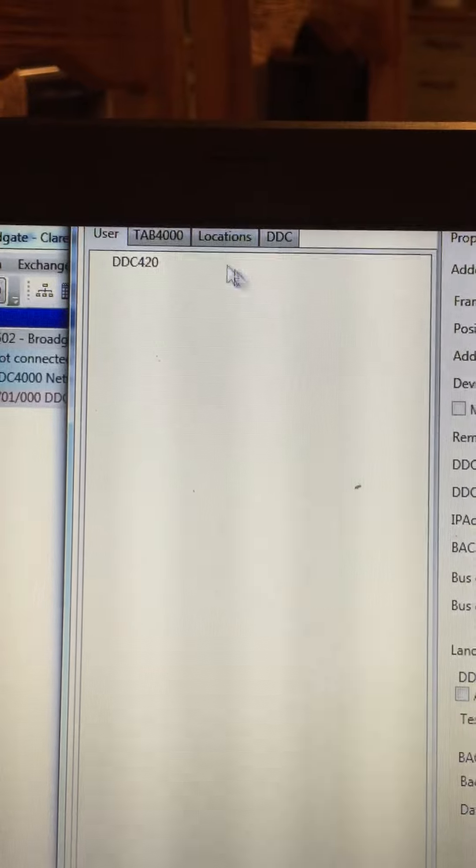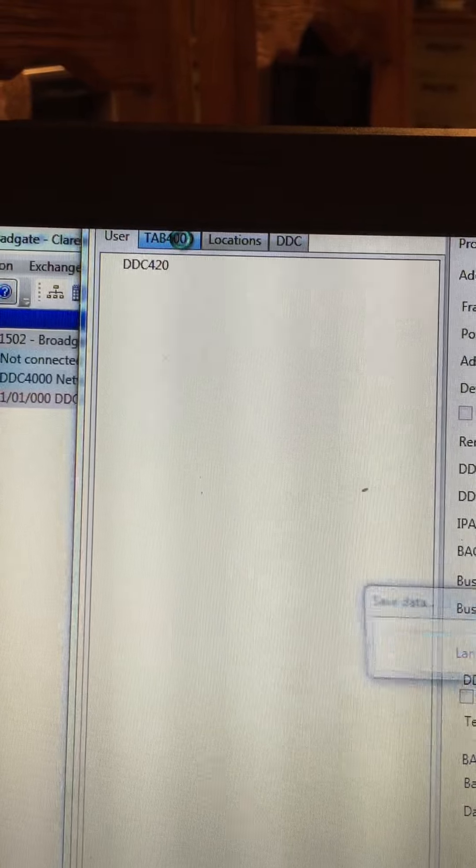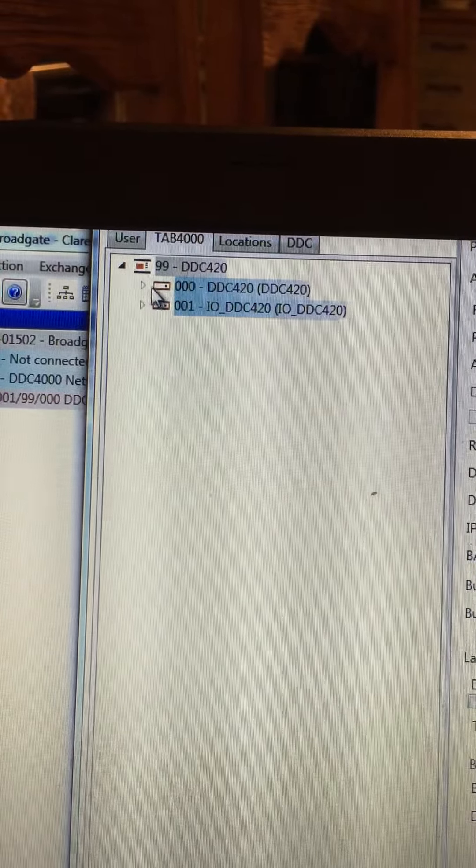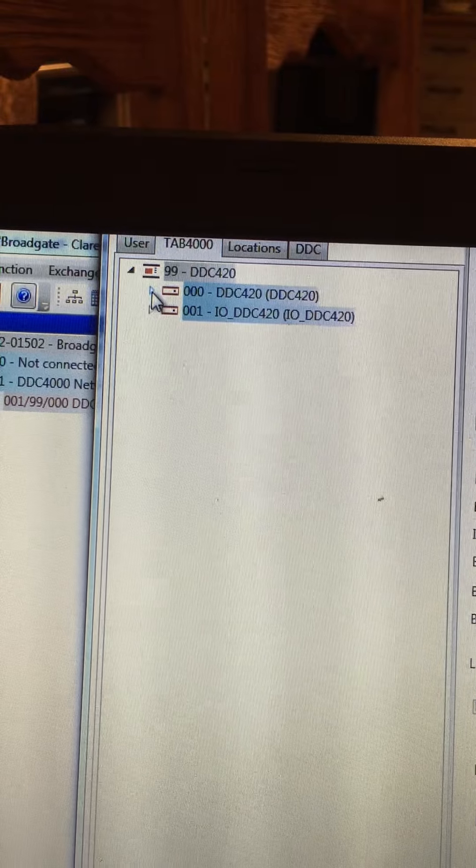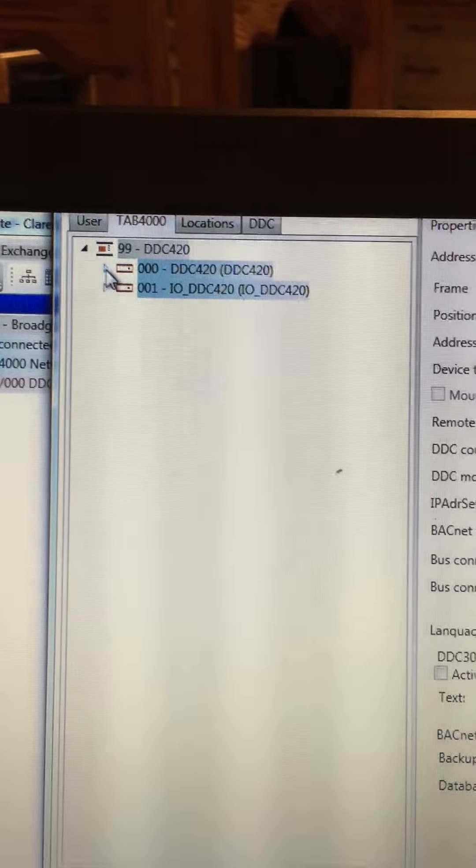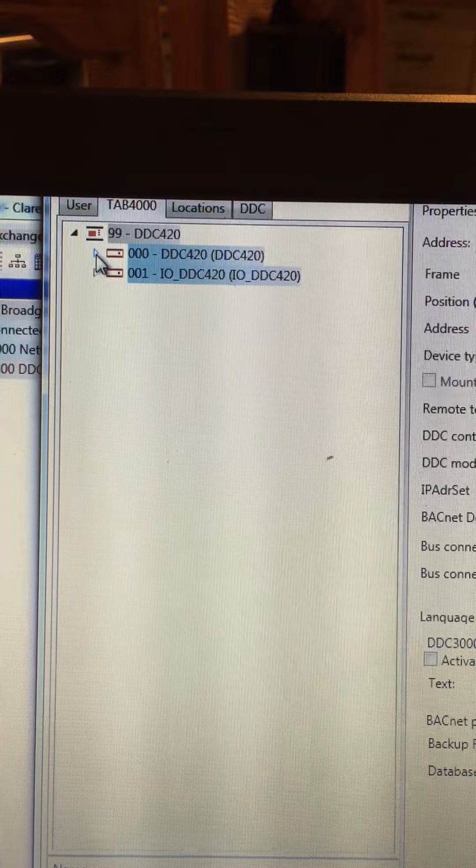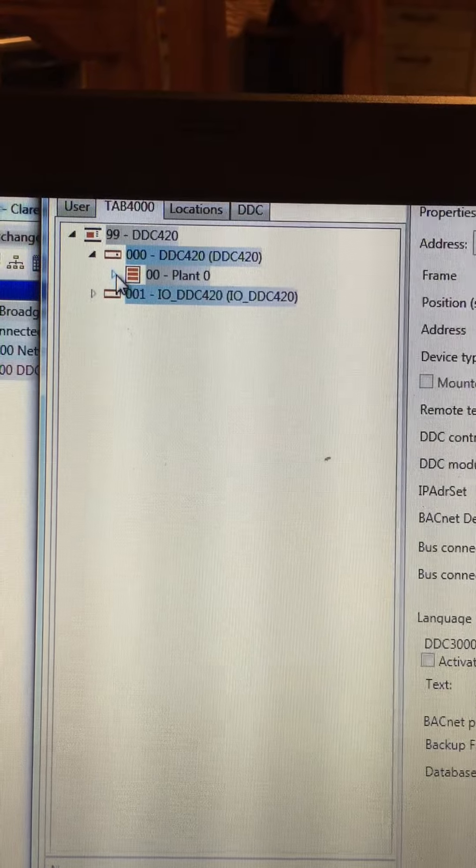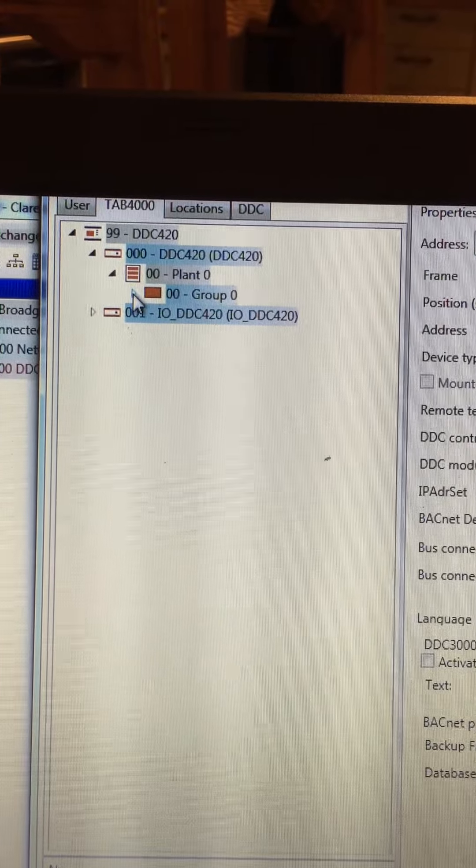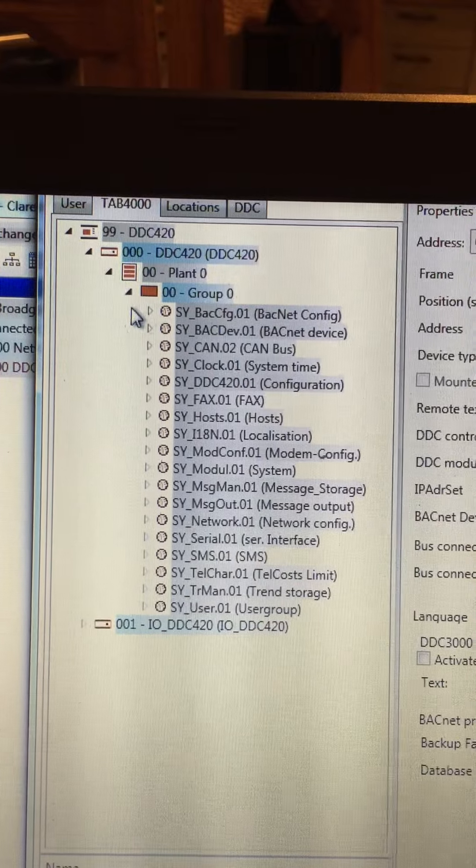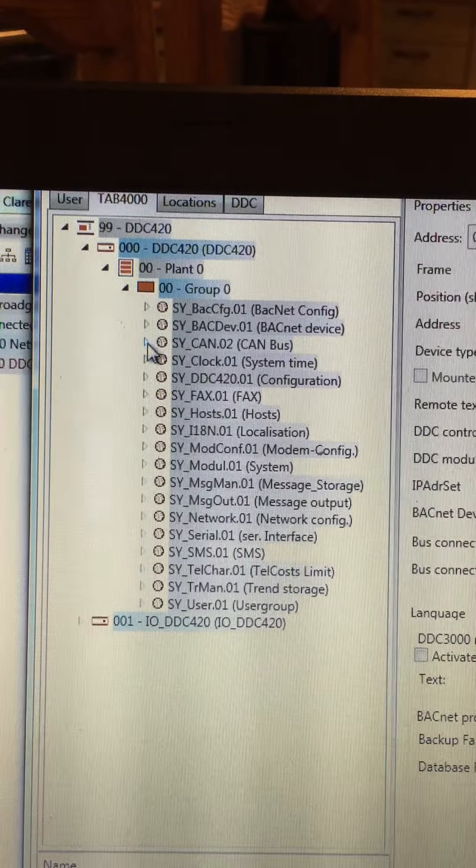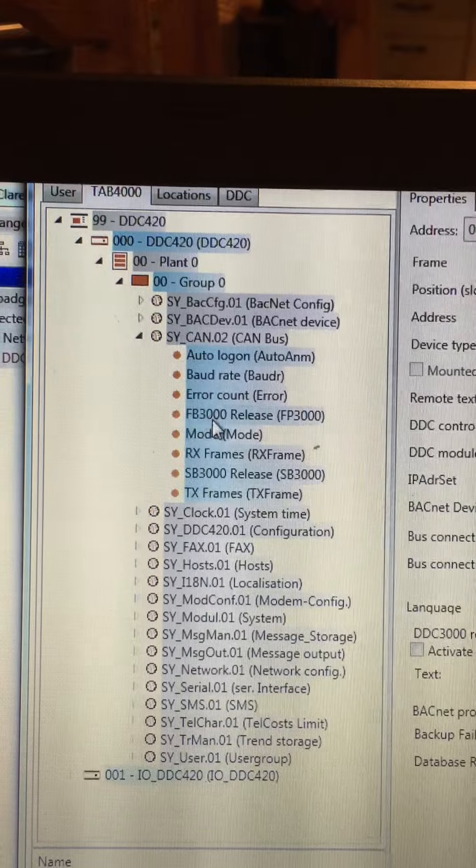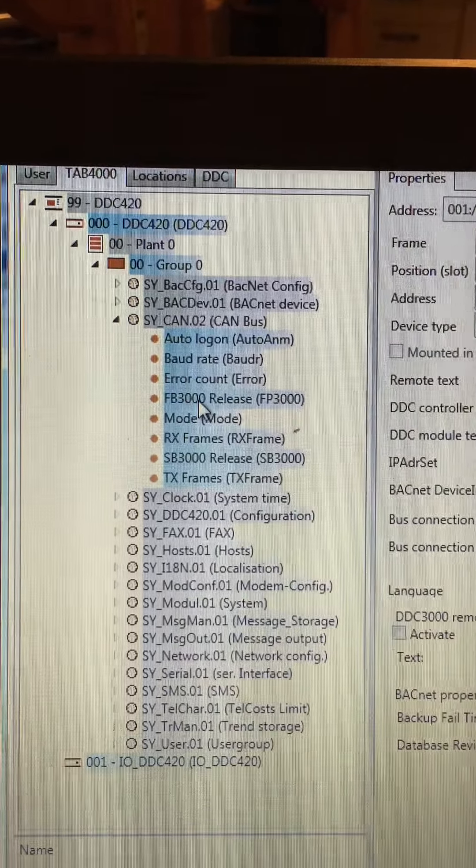If I go to the tab 4000 page, I can start to commission the controller settings for the CAN bus operation and also the BACnet operation. So if I expand the group 0 and expand plant 0 and then the next group, I can go to canvas and we enable the field bus 3000.